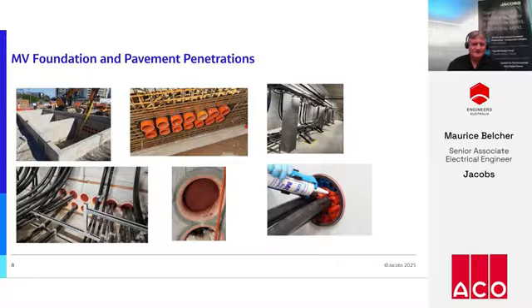In the bottom right-hand side I've shown examples of sealing. One of the biggest issues with in-ground infrastructure and penetration through slabs and pavements is water egress. There's a good example of how spare conduits on the left-hand side are sealed with a proprietary product to give you both watertight and fire rating through those penetrations.